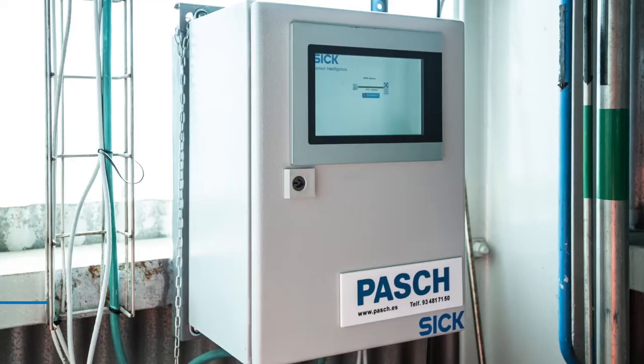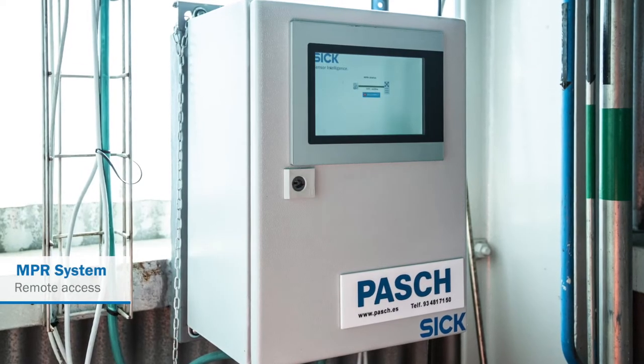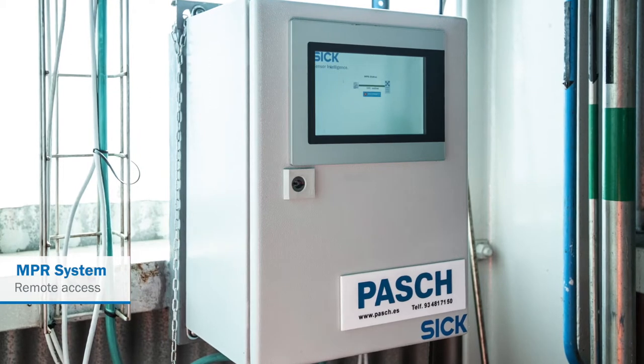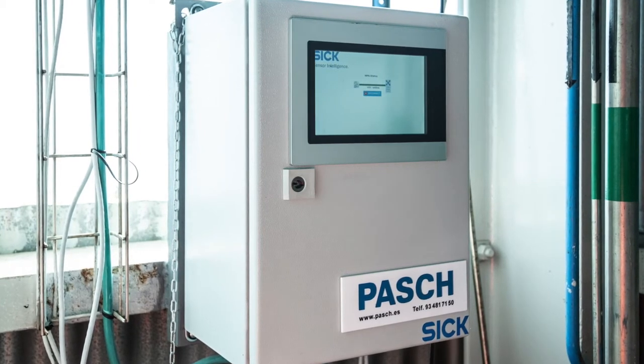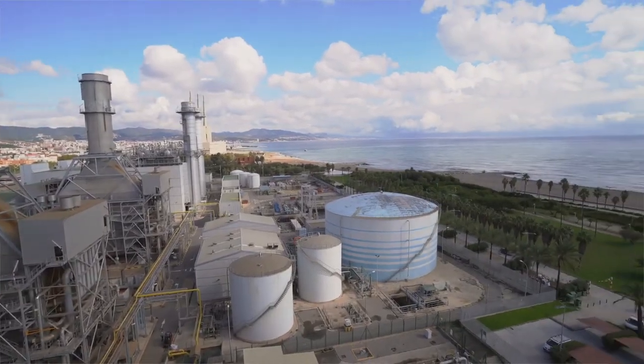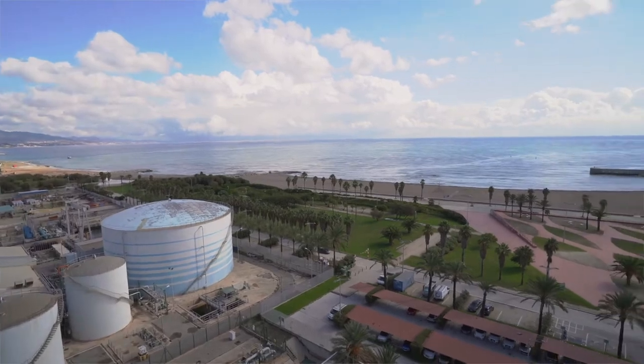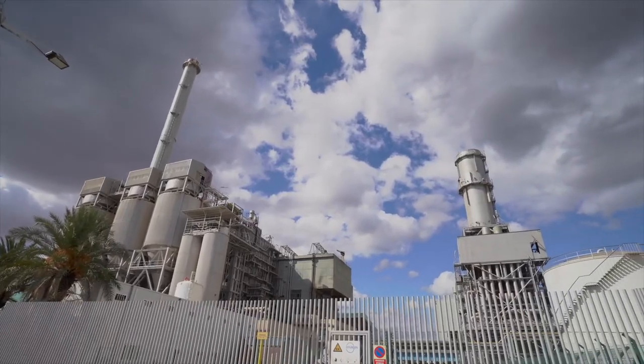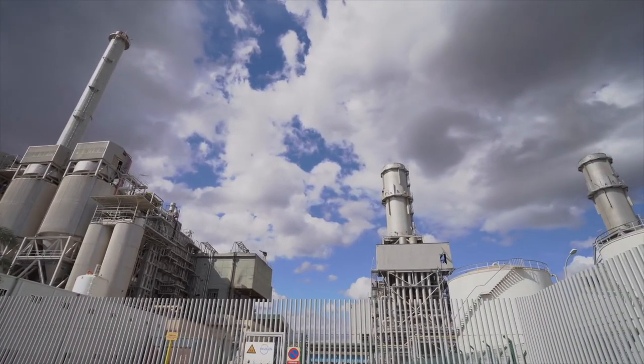We want to highlight that during the COVID-19 period, thanks to the connection via the meeting point router MPR, we had the opportunity to perform diagnosis and maintenance of the analyzers, monitoring the alarms, carrying out QAL3 checks and adjustments, and most importantly, achieving continuous uptime without any interruption of this plant, which is considered an essential service.